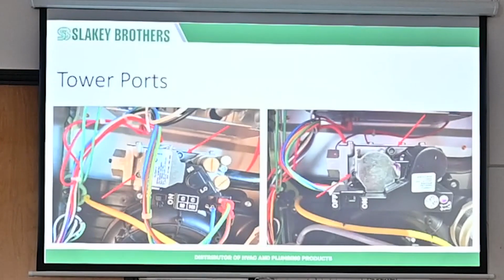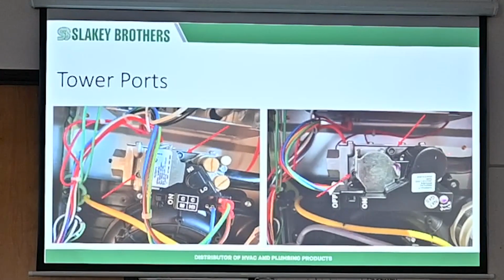The reason being, it will hit on a little bit later in the diagnosis. When this thing trips on a regular old limit switch fault, it doesn't just reset and try again like a traditional single stage furnace would. If this thing trips too many times, it won't just shut down and lock out like a regular furnace will. It will actually ramp up and go 100% airflow and 100% gas flow.